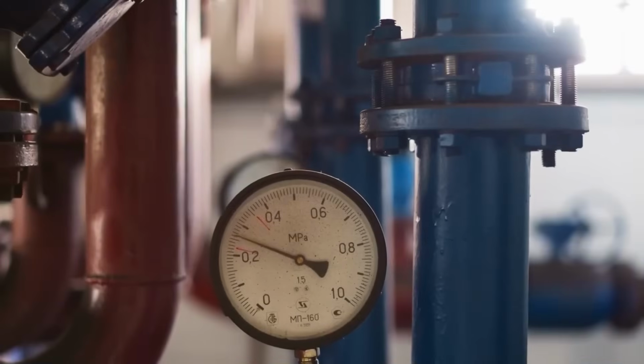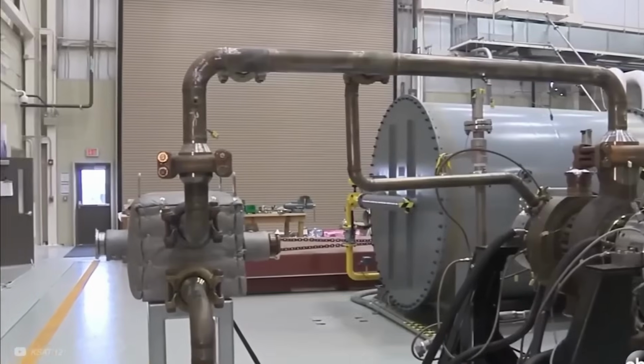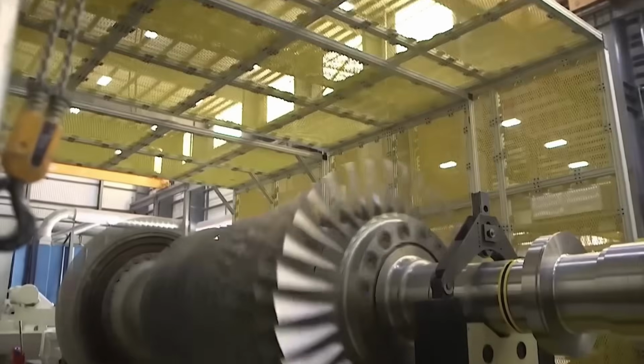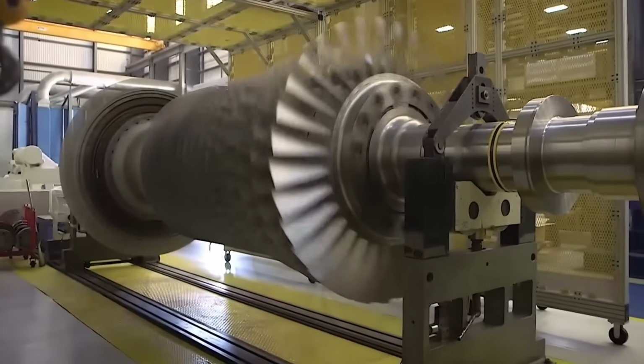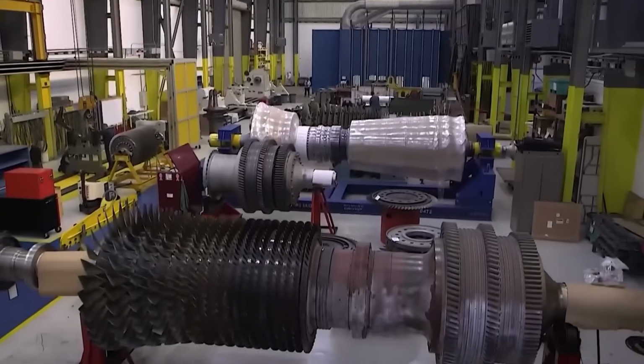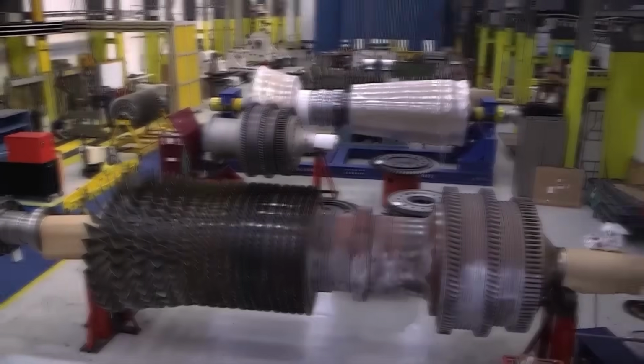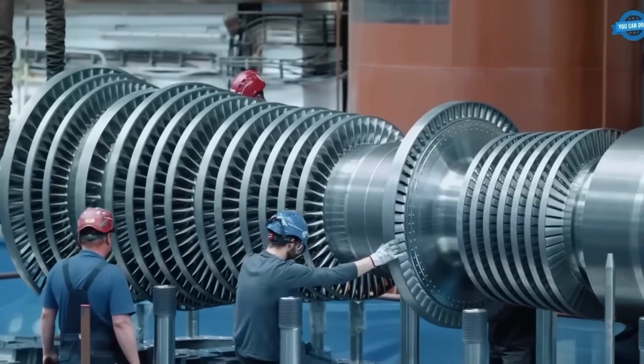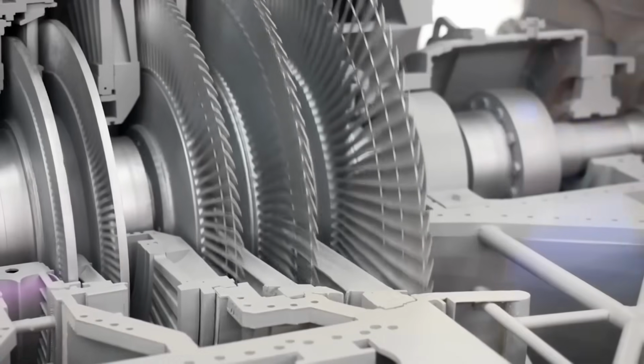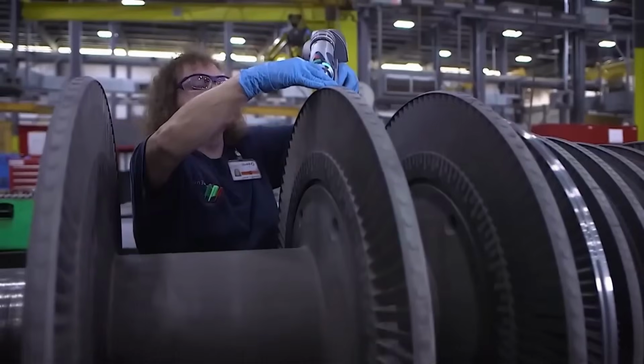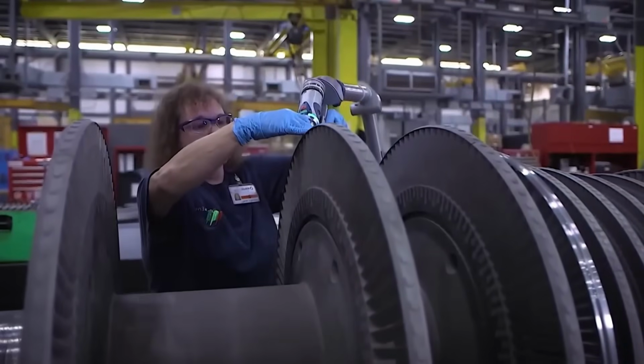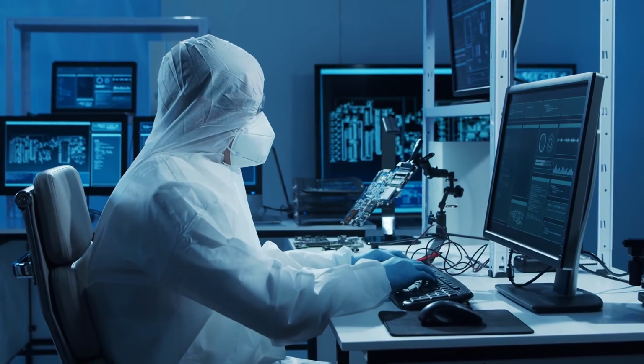And then there is speed. A smaller turbine has to spin faster to produce the same power, often tens of thousands of RPM. Normal oil bearings would cook themselves within hours at that speed, so engineers had to invent entirely new bearing systems, some using magnetic levitation, some floating on a thin cushion of the carbon dioxide itself. Both work. Neither has decades of real-world proof behind it.